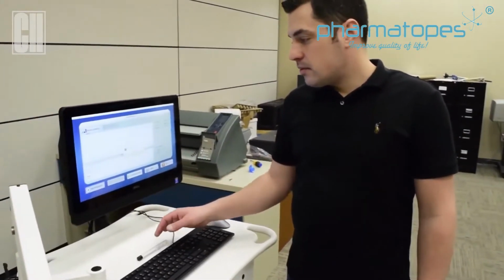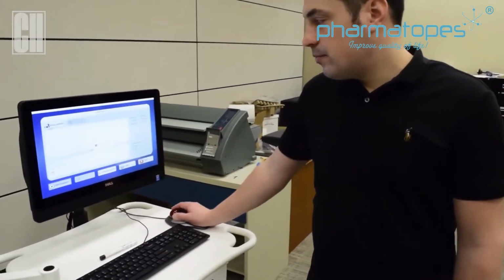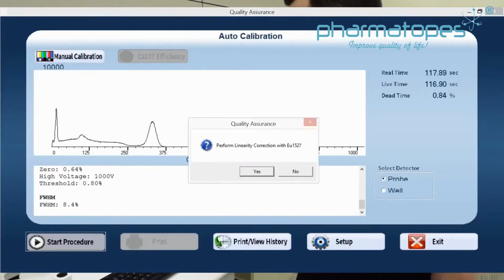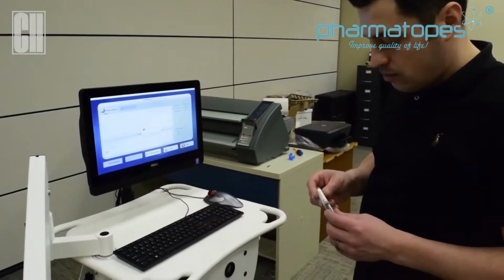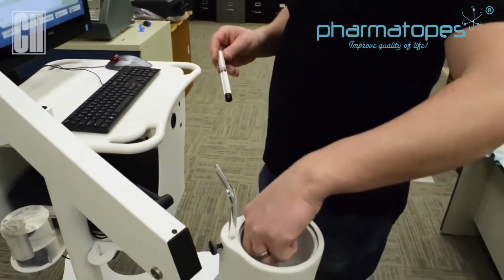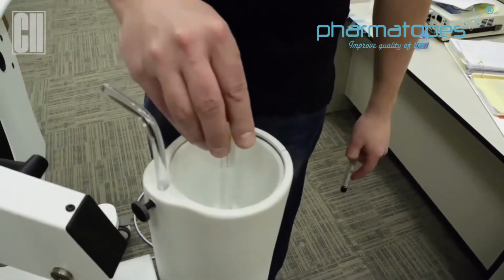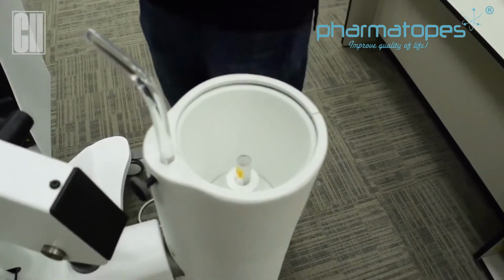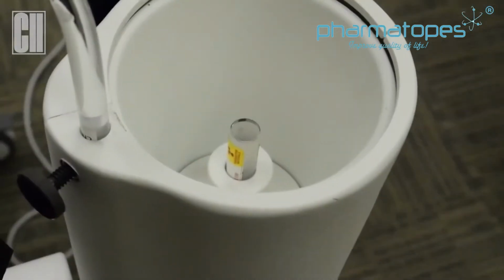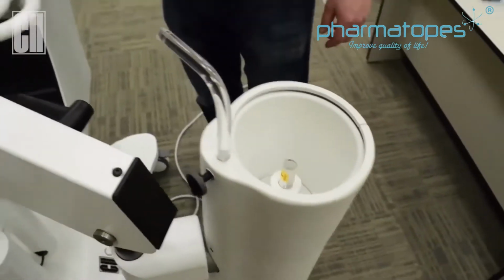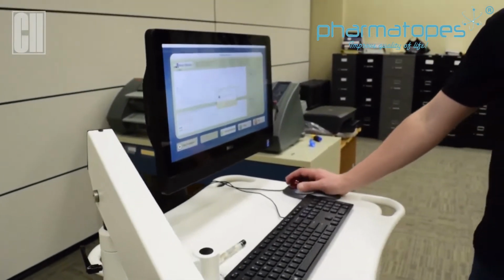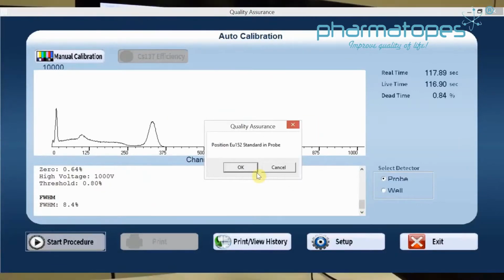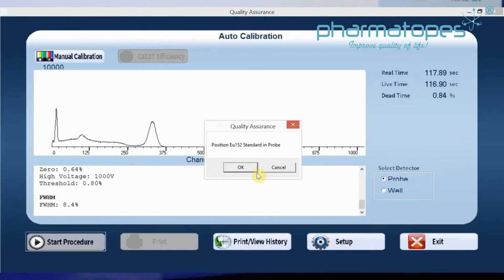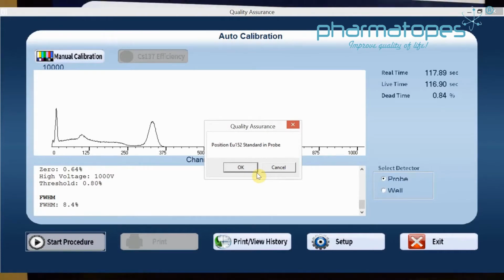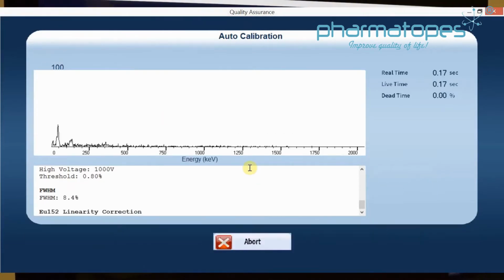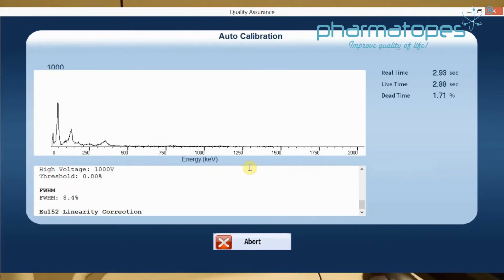Once the calibration is successful and it finishes the calibration with cesium, it will ask us to perform linearity with your europium source. So you want to grab your europium source, remove cesium, place the europium source into the probe with the black tip down again. Once that's in place, we can click on yes to perform the linearity. Once we have the source lined up, we can continue on with the linearity, and we can position the source into the probe, click on OK, and it's going to calibrate our europium and give us a linearity result.